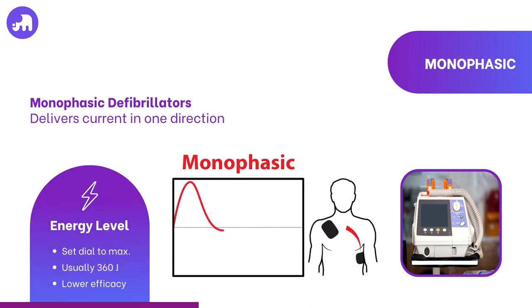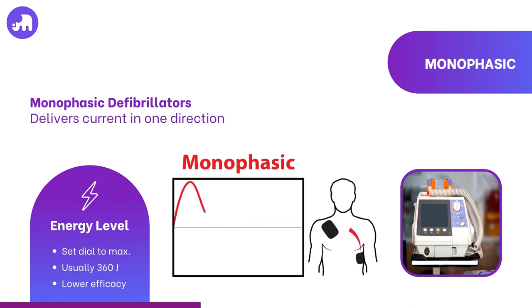Monophasic defibrillators work by delivering a single directional shock from one paddle to the other, with energy transferred in one direction across the heart. When using monophasic defibrillators on adults, they usually initiate defibrillation at a higher energy level, often between 200 to 360 joules. This higher energy requirement is due to the unidirectional nature of the shock, and subsequent shocks may necessitate increased energy if the initial shock is unsuccessful.